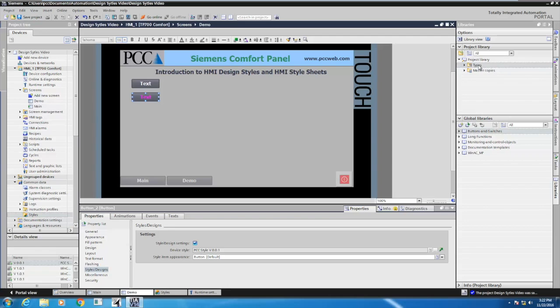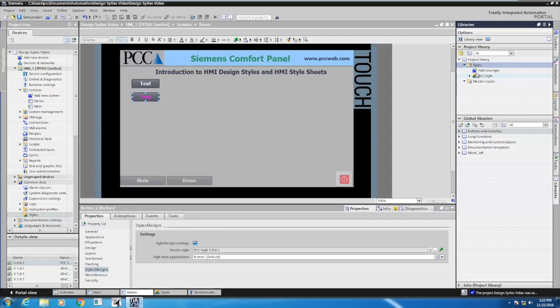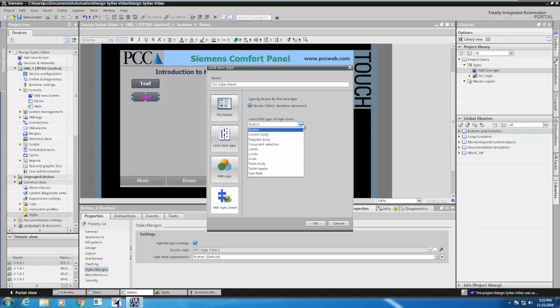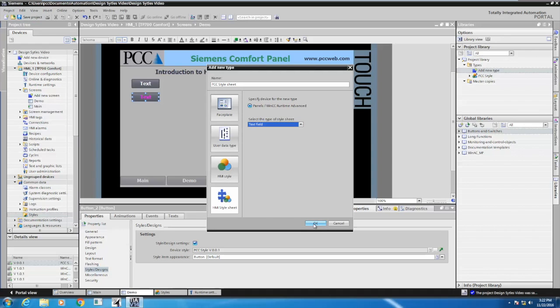In the types area I'm going to add a new type. This time, instead of picking an HMI style, I'm going to pick an HMI style sheet, and I'm going to call this one the PCC style sheet. Then you have to select the type of style sheet — this controls which attributes of which objects you're going to be able to apply or utilize. I'm going to select text field and say OK.